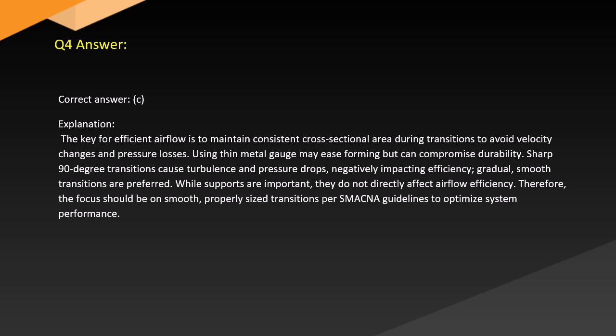Sharp 90-degree transitions cause turbulence and pressure drops, negatively impacting efficiency. Gradual, smooth transitions are preferred. While supports are important, they do not directly affect efficiency. Therefore, the focus should be on smooth, properly sized transitions per SMACNA guidelines to optimize system performance.